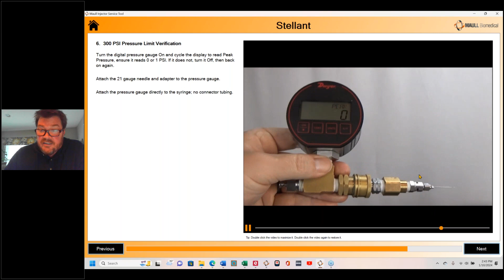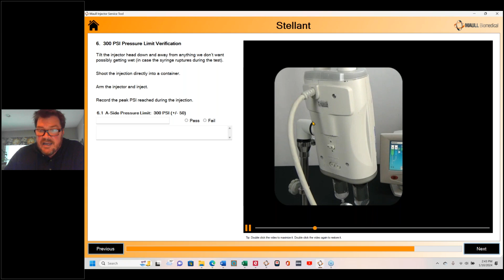So now we're actually going to perform the injection. And then obviously the pressure limit check, we're showing the operator, or the technicians or the BMETs, how to go through the actual injection. Always tilt the injector head down. We have our injector connected to the syringe. We're going to just shoot the water back into a container and then measure the pressure on our injector. Remember, it was 300 psi, so we're looking for 300 psi plus or minus 50, and that's the range we're looking for. So we will say pass. We got 310, whatever we got there, I forget. And on to the next.